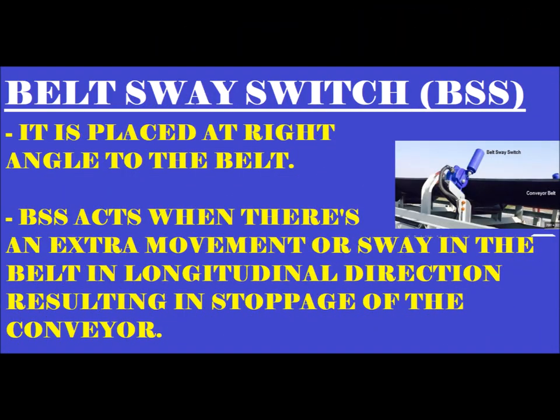The second component is the belt sway switch (BSS). The BSS is mounted at a right angle to the conveyor belt. It works when the belt moves in the longitudinal direction — if the belt moves to the right or left side instead of its straight path, this is called belt sway. Movement to either side can damage the belt due to wear and tear, so the BSS is used to detect and stop the belt to prevent damage.